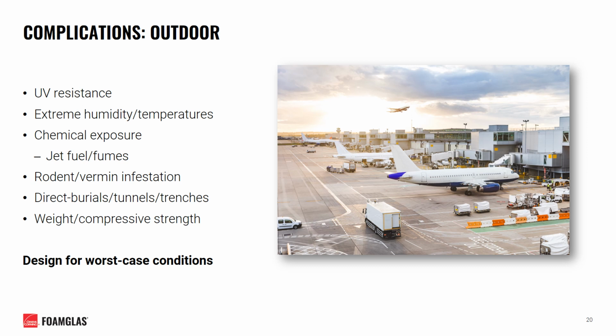Similar to indoor environments, outdoor chilled water systems may be subject to additional risk factors that need to be considered. It is imperative to ensure any materials subject to direct sunlight have adequate UV resistance. Seasonal extremes in temperature and humidity will also need to be determined and taken into account.